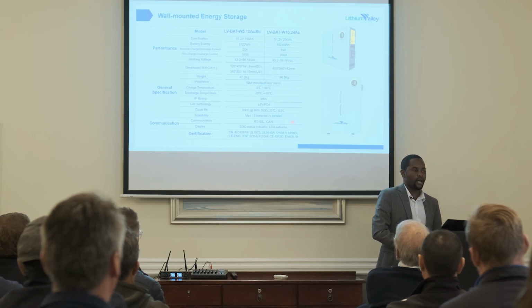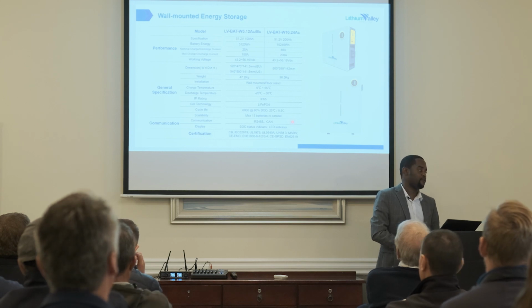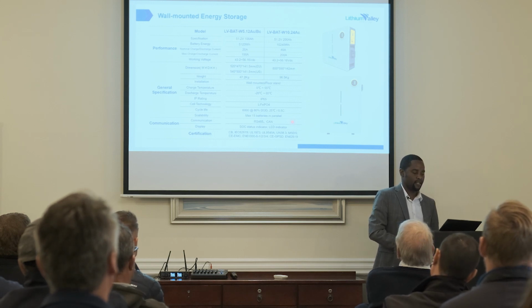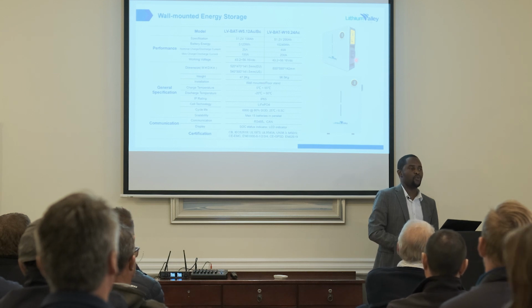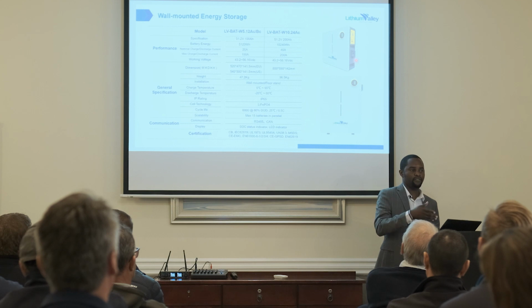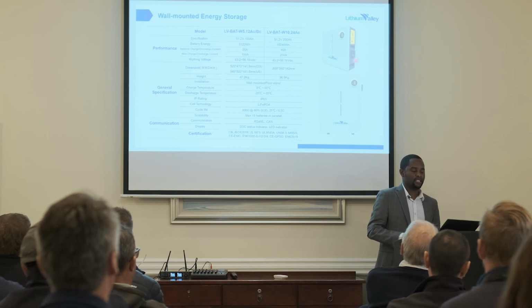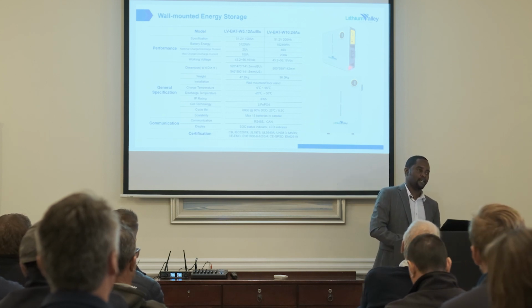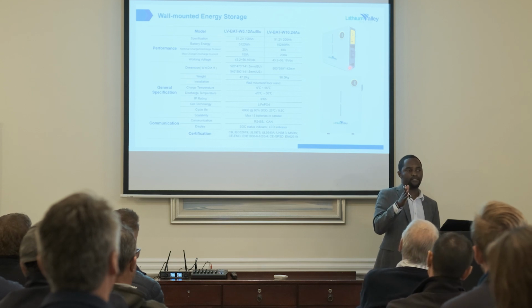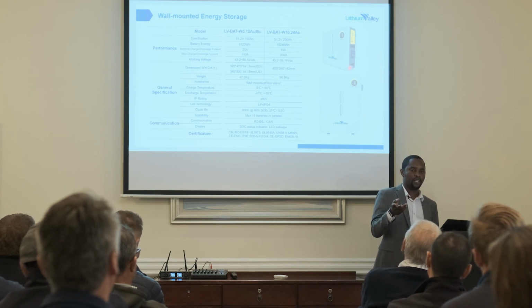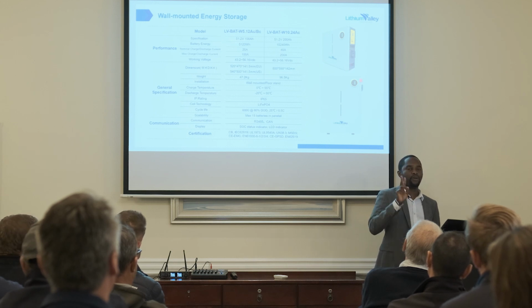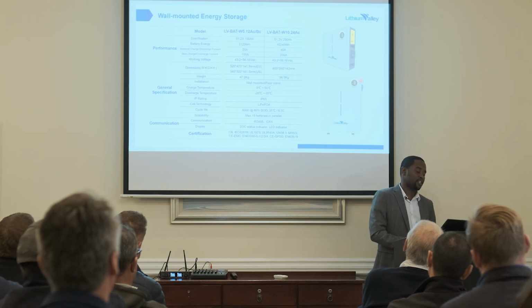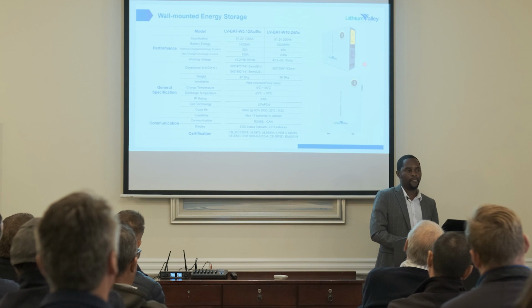It has got a fuse disconnect by the side. I think it can be seen here. So what it means now is you don't need to go and buy that fuse holder and the holders, you have it. The other batteries in the market that attempt to have such only break one line, the positive. And with the SANS regulations now, they require to break both. But now with this lithium battery, you are breaking both the negative and the positive. So you've got enough protection on that. It's a 125 amp, right?